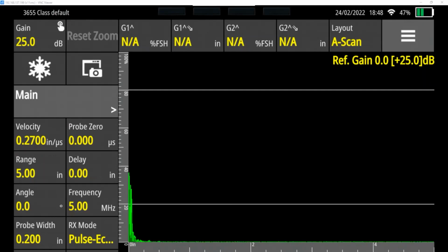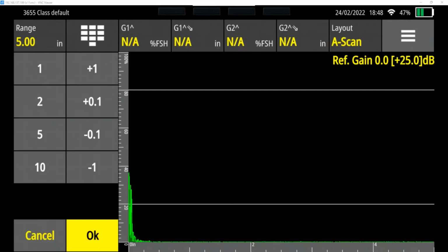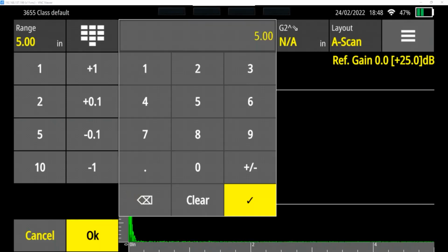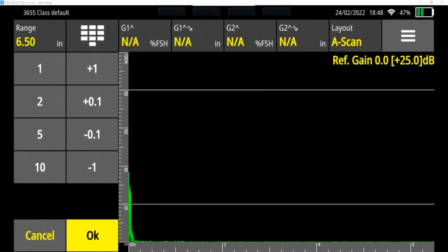The range: this block is 3 inches tall, and what we're going to use is a backwall echo and then a secondary backwall echo to do it. So the backwall echo is at 3 inches exactly. A secondary echo is going to be twice that, so 6 inches. So I'm going to adjust this to be a little bit over that. I'm going to go to 6.5 inches here. So across the bottom of the screen, we can see 0 to 6.5 inches.